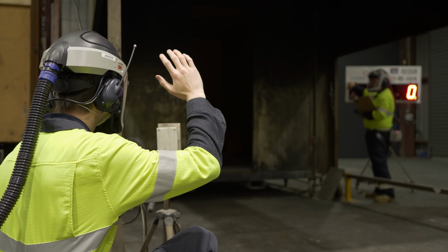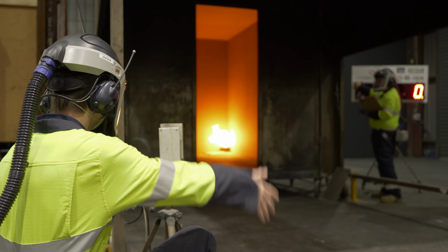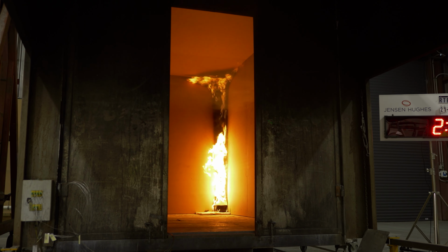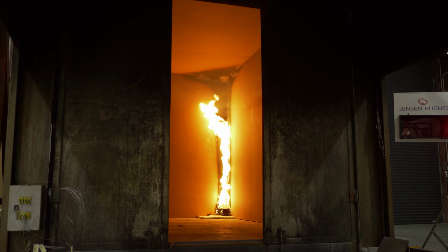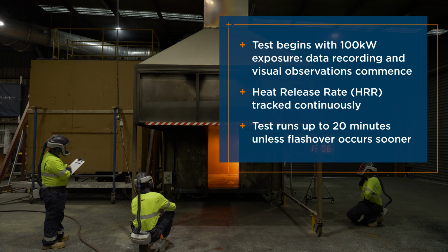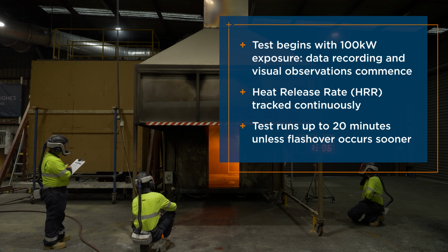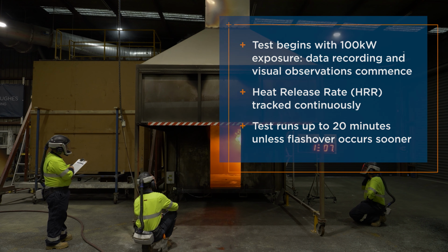The specimen is exposed to a specific gas-fired burner placed on the floor in one corner of the room at an initial output of 100 kilowatts. Observations of significant events are made. The data is continuously recorded to allow ongoing calculation of the total heat release rate.